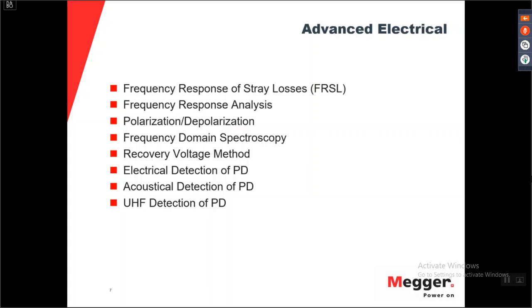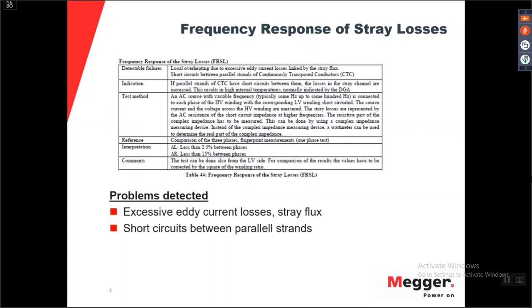So we will cover the top 5 tests, but I will split them only into 3 because the last 3 is actually the same. So with that, we go to the CIGRE technical brochure for frequency response of stray losses. Now we will be a little bit more theoretical than part 1 because we need to understand the tests a little bit more than for the more simple winding resistance test.